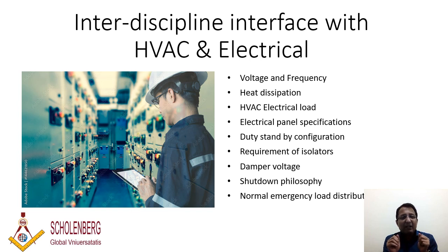In that requirement, you don't want your laundry fan to run, you don't want your kitchen fan to run, you don't want your toilet fan to run. You can tolerate those 4 hours without that. So you are reducing the load and putting it on the diesel generator, which will provide the air conditioning just enough for 4 hours for those people gathered at that location.